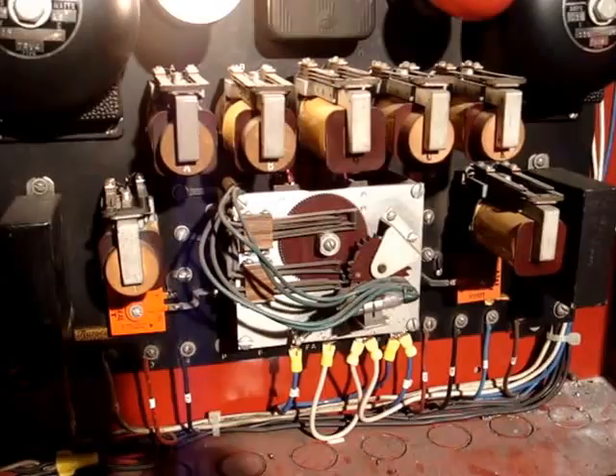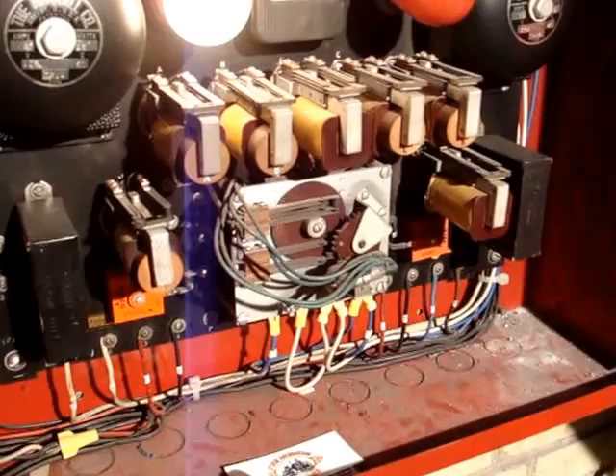And we can turn that trouble bell off so we don't have to listen to that. Now this will go approximately 1 minute to do the complete 4 rounds. And it's on the last round right now. And as you can see, it automatically stops. The B and the J relay work together, and it automatically stops the synchronized motor from turning the code wheel. And that's it.